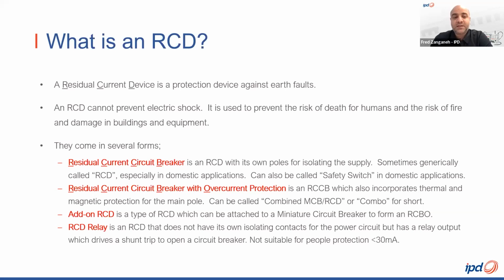Yeah, and RCDs can come in several forms. A residual current circuit breaker, or RCCB, is an RCD with its own poles for isolating the supply, sometimes generically called RCD, especially in domestic applications. They can also be called safety switches in domestic applications as well. And we also have an RCBO. And I'm often asked, what does an RCBO actually stand for? Its technical name is the residual current circuit breaker with overcurrent protection. And this is effectively a residual current device that also incorporates the thermal and magnetic protection for the main poles. This can be called a combined MCB-RCD, or in the industry, we often call it a combo, just for short.